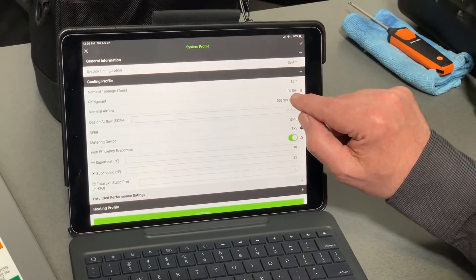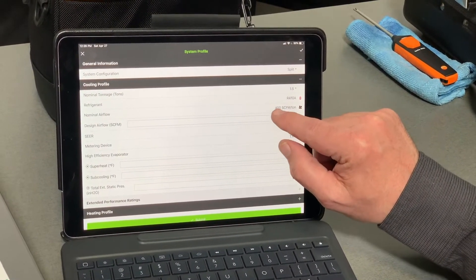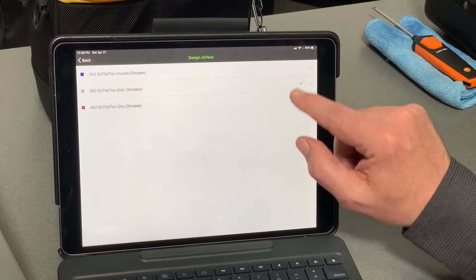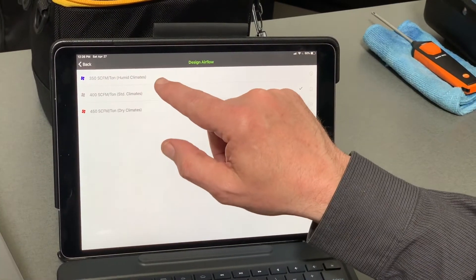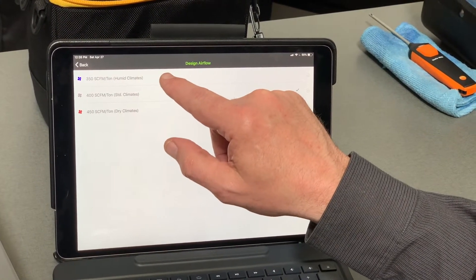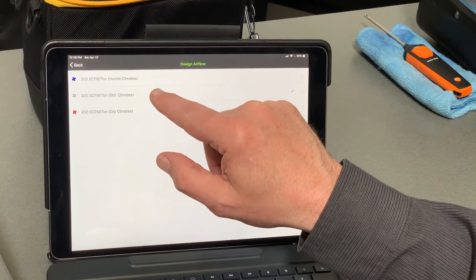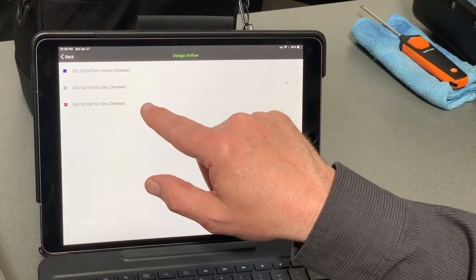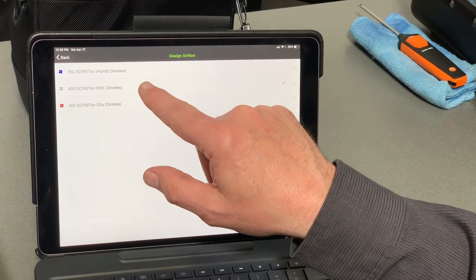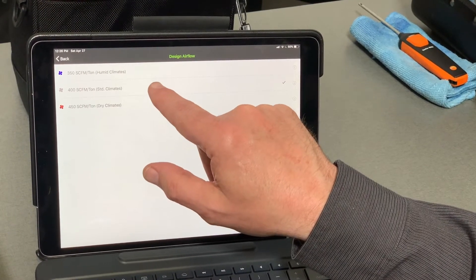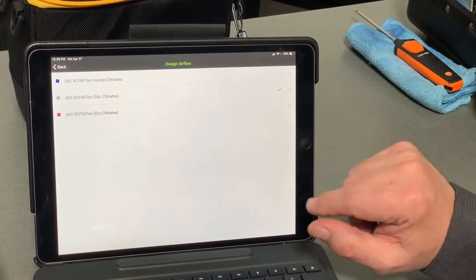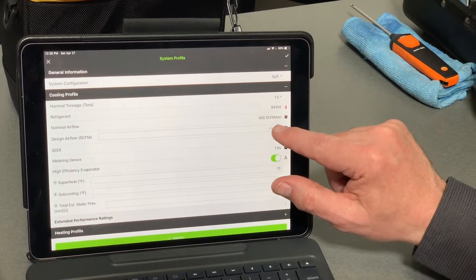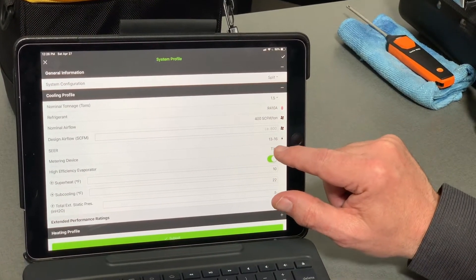For nominal airflow, if you don't know what that is, there are basically three different airflows: humid climates like Florida, standard climates like Ohio, Michigan, and Indiana, or really dry climates like Arizona. Typically most guys in the country are going to be using 400 standard CFM per ton, so we're going to leave that one checked as it is.